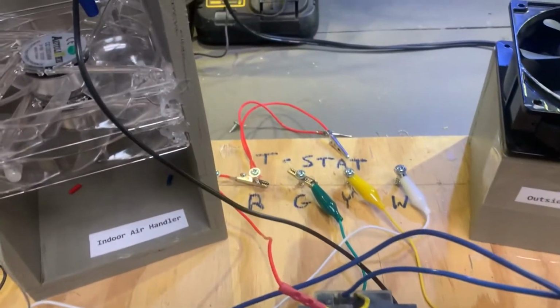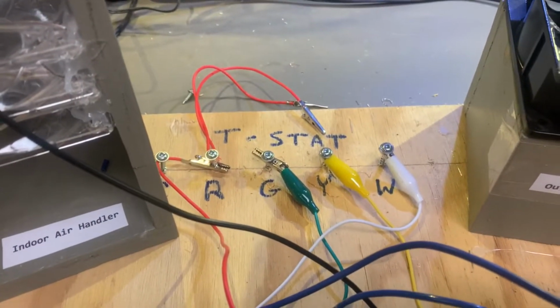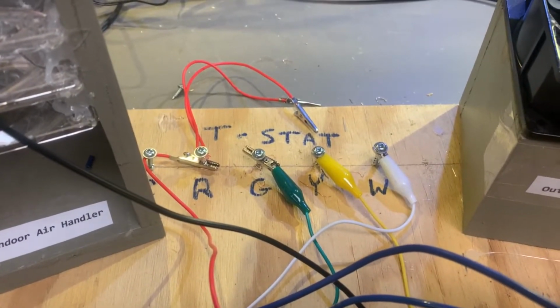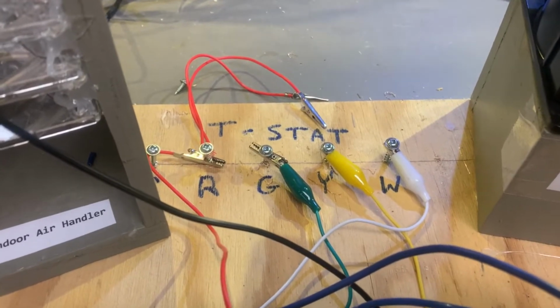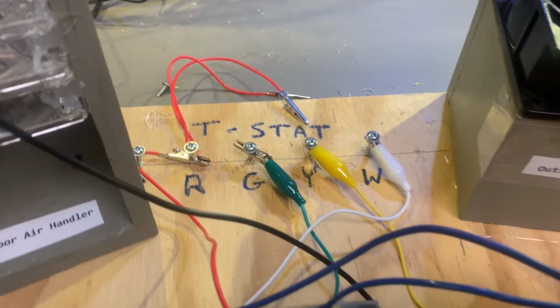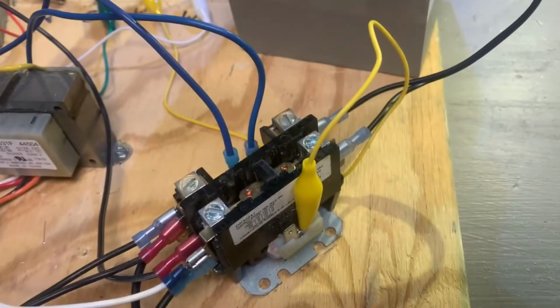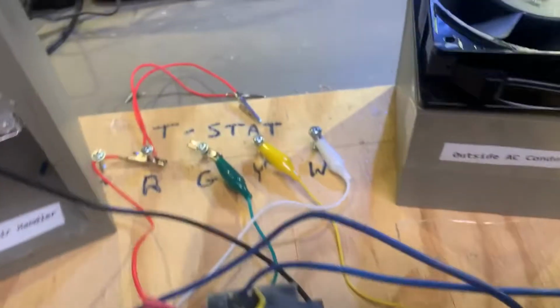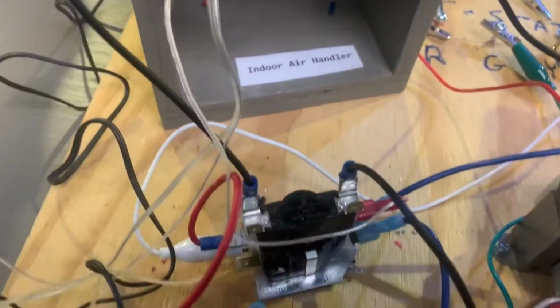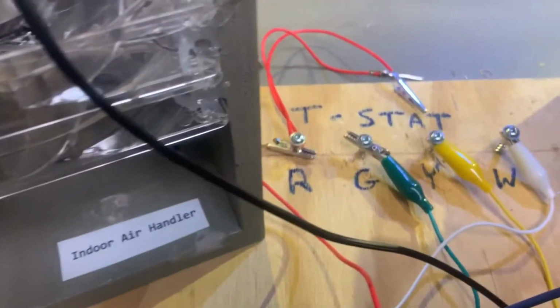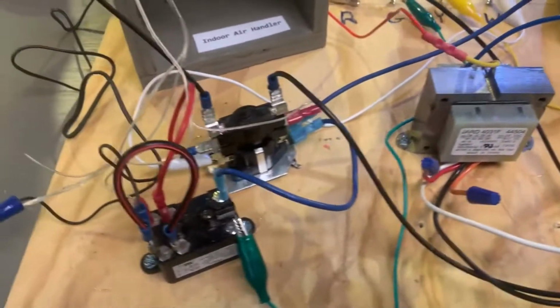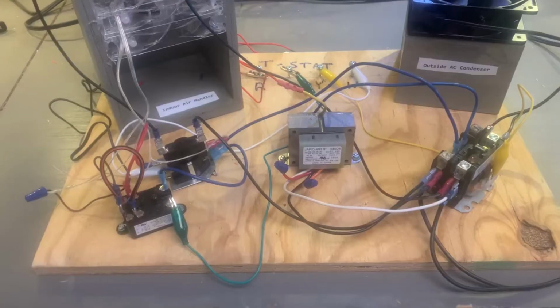Okay, this area up here is going to act as our thermostat. The colors are the same as they would be in a real thermostat, and I have properly colored jumpers going to the appropriate relays. As you can see, our yellow here is coming over to the contactor. White is coming over here to the sequencer, and green is going to the fan relay right here.